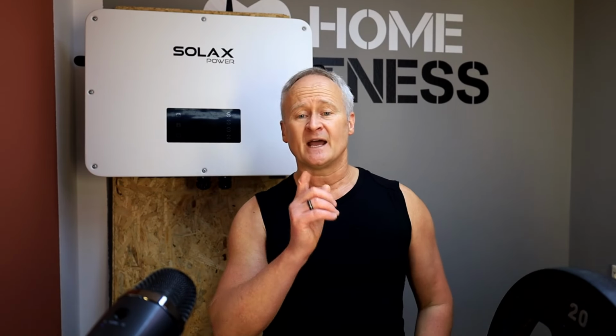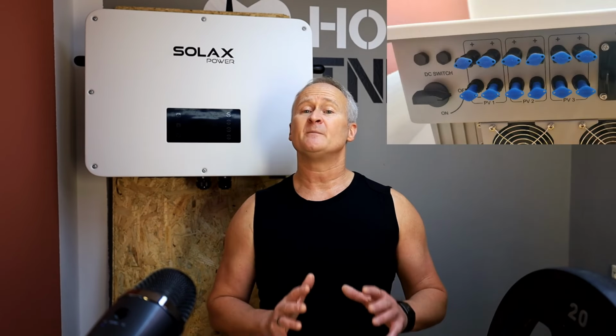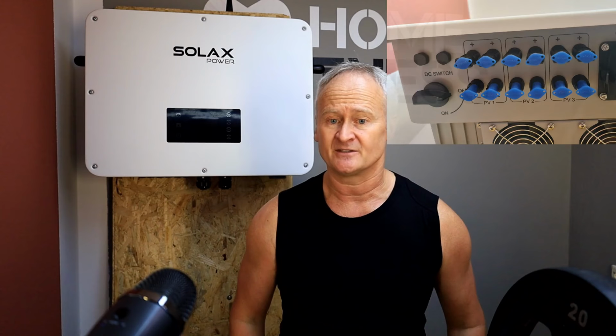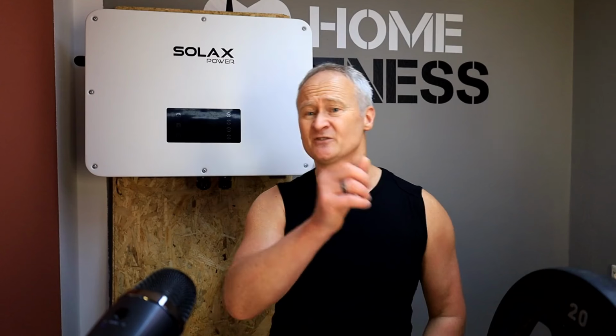Furthermore, all versions of this system share the important characteristic that the peak power of the modules you can connect can be up to precisely twice the maximum AC output power. This is made possible by the fact that each individual MPPT tracker has two parallel electrical connections and can draw up to a maximum of 36 additional amps from the modules during continuous operation. How to properly and effectively use parallel connections on an MPPT tracker is something I thoroughly explained in a previous video.